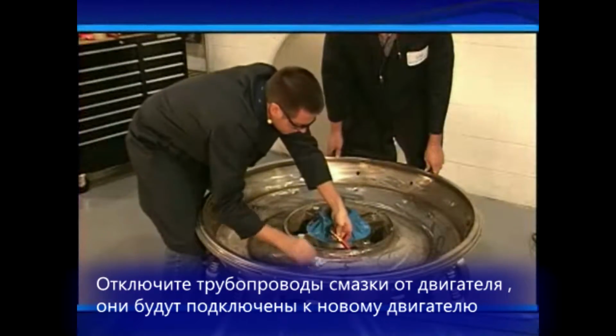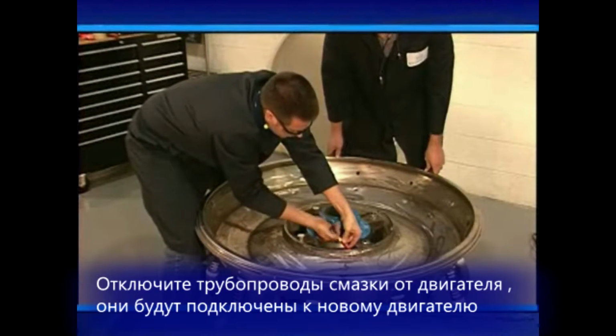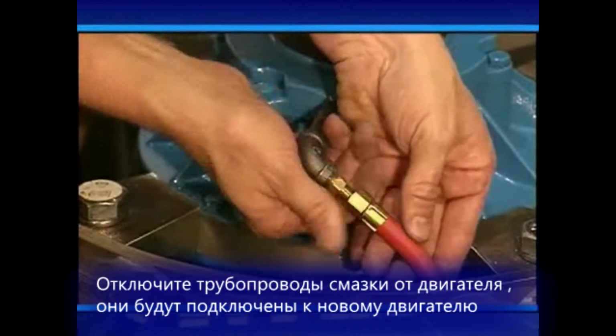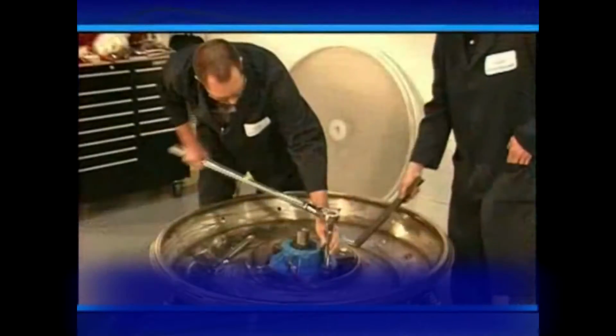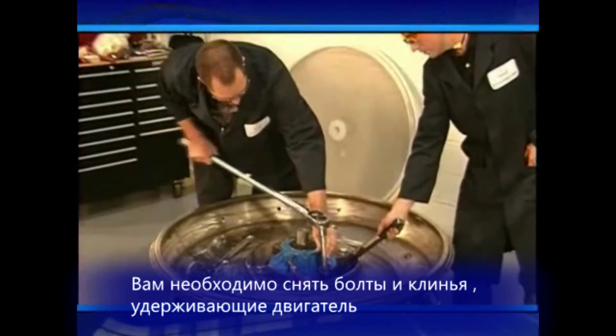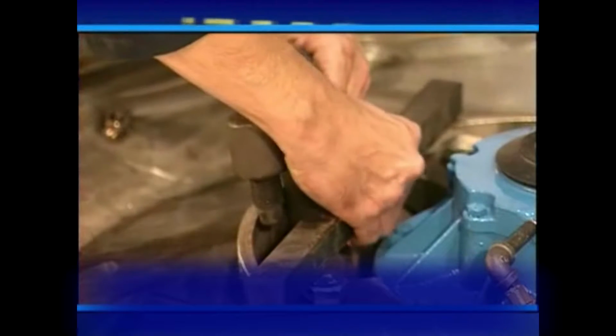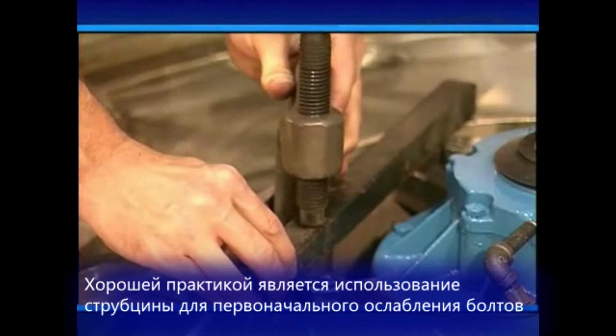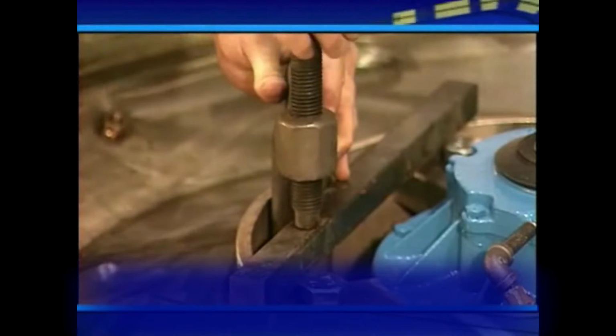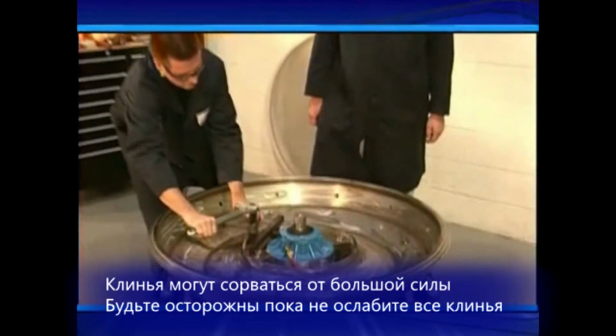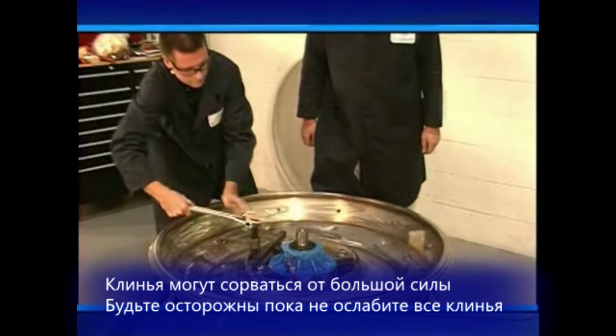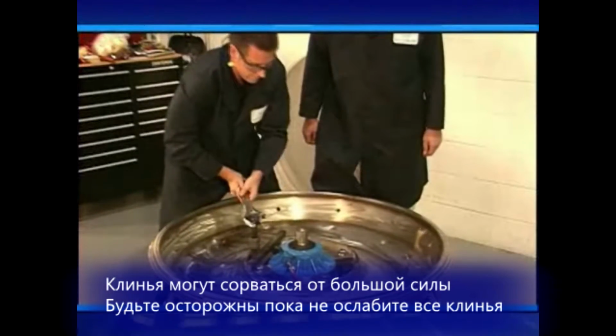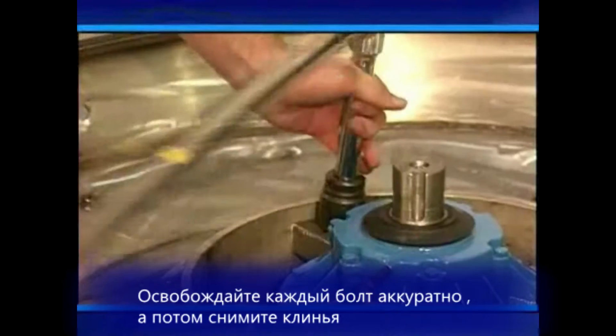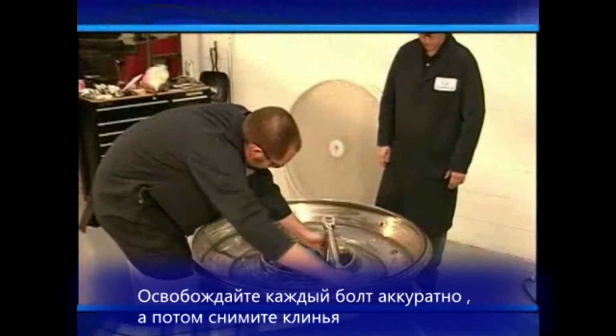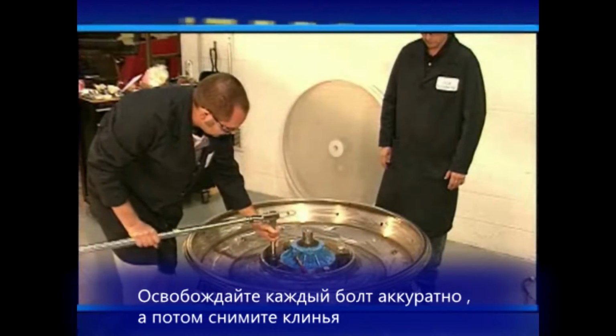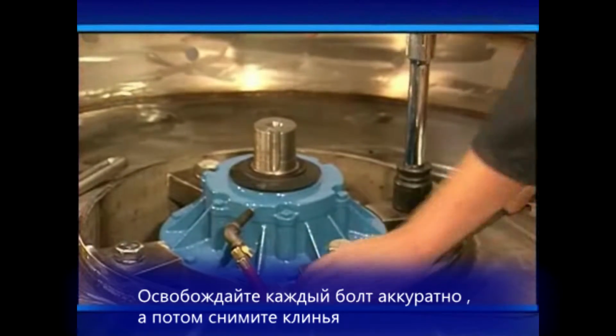Disconnect the lube lines from the motion generator. These will be reconnected once the new motion generator is installed. You'll need to remove the bolts and the lock washers from the motion generator. It is a good practice to use a C-clamp and to secure a guard when initially loosening. The wedges may break loose with great force, so keep the threads on the bolts engaged until all wedges move freely. Unthread each bolt carefully, then remove the wedges.